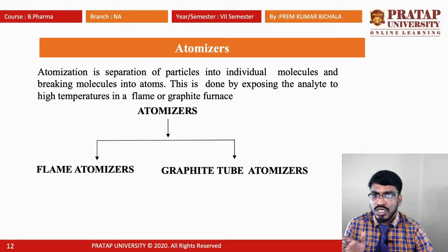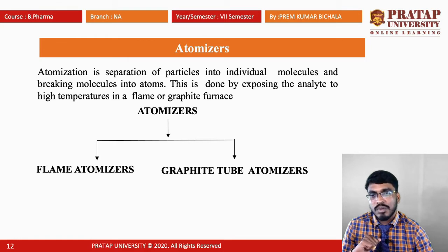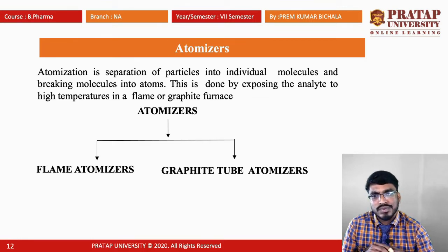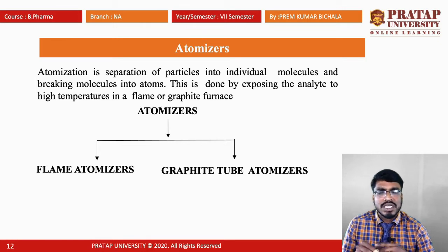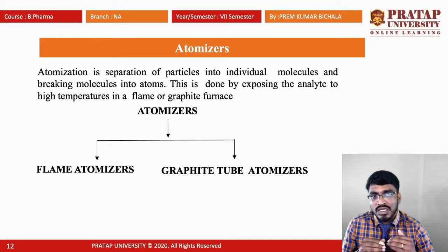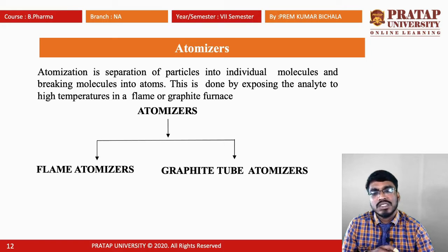As mentioned, the aerosol is carried to the atomizers. The atomizer is one of the basic parts of the equipment. Atomization is a separation of particles into individual molecules and breaking of molecules into atoms. This is done by exposing the analyte to high temperatures in a flame or a graphite furnace. The sample first reaches the nebulizer, where it is converted into vapor state. Those vapors travel to the atomizer, where the flame occurs and the analytes may be excited. There are two types of atomizers: flame atomizers and graphite tube atomizers.